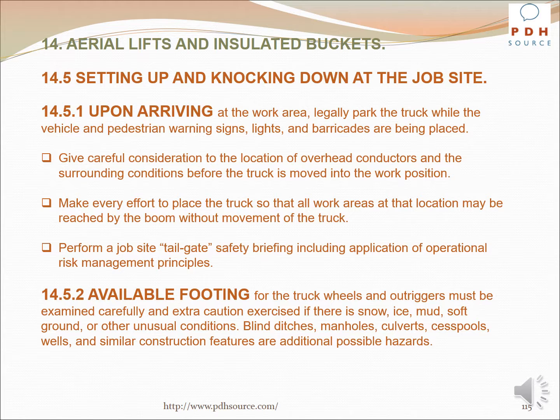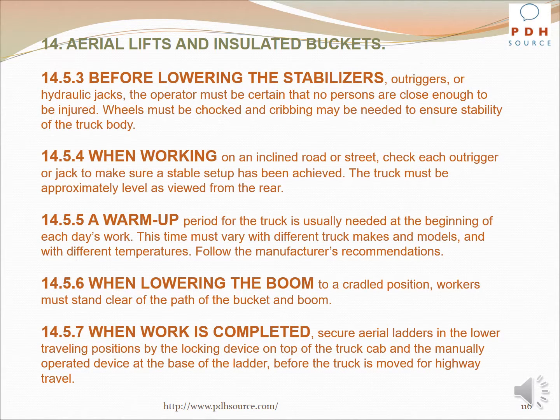Available footing for the truck wheels and outriggers must be examined carefully and extra caution exercised if there is snow, ice, mud, soft ground, or other unusual conditions. Blind ditches, manholes, culverts, cesspools, wells, and similar construction features are additional possible hazards. Before lowering the stabilizers, outriggers, or hydraulic jacks, the operator must be certain that no persons are close enough to be injured. Wheels must be chocked and cribbing may be needed to ensure stability of the truck body. When working on an inclined road or street, check each outrigger or jack to make sure a stable setup has been achieved. The truck must be approximately level as viewed from the rear.